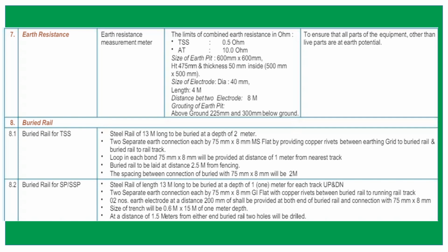And buried rail in SP and SSP is below 1 meter from the SP SSP surface level, and 13 meter long same rail is used for each up and down line. Two separate earth connection, each of 75 into 8 millimeter GI flat with copper rivets between buried rail to running track. 2 numbers earth electrode at a distance of 200 millimeters shall be provided at both the ends of the buried rail, and connection with 75 into 8 millimeter size, the trench size they have given, at a distance of 1.5 meter. For SP and SSP, the distance of the two holes is 1.5 meter.